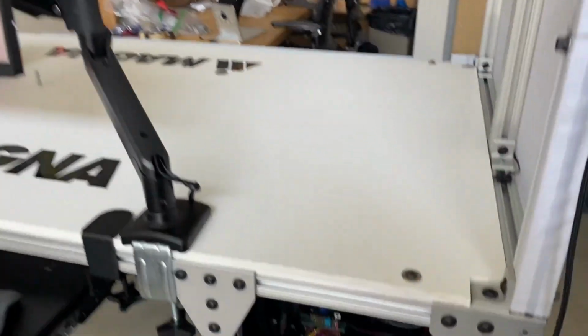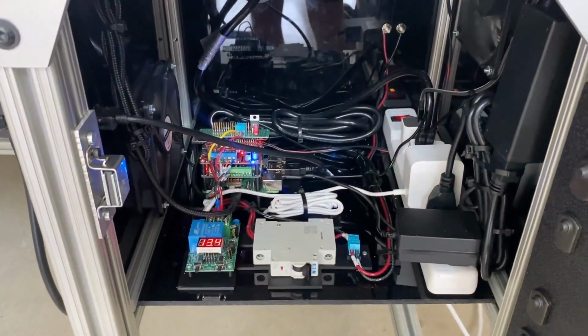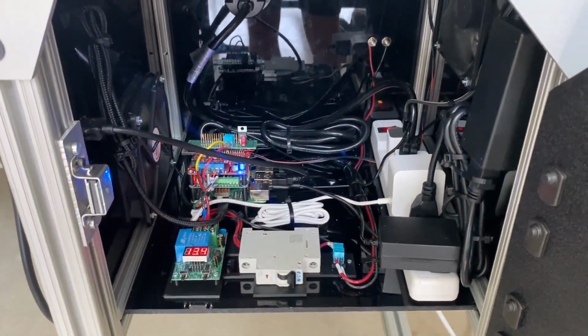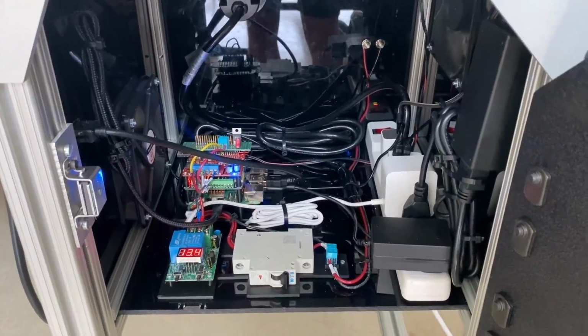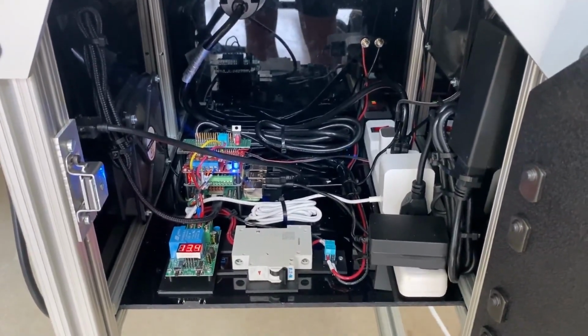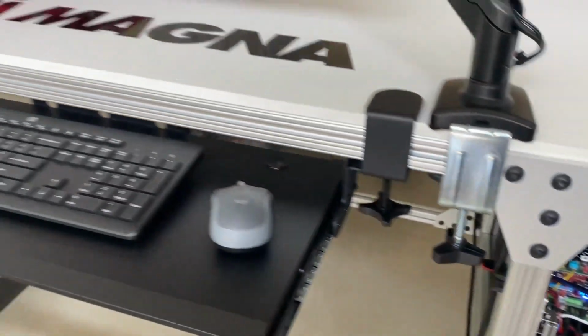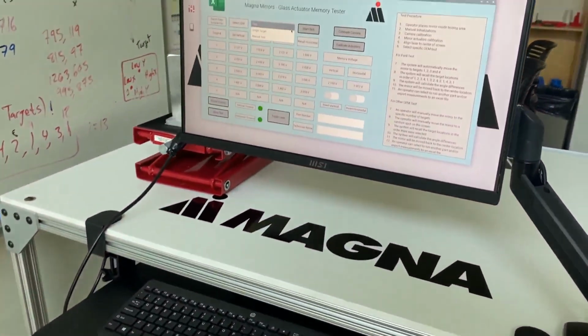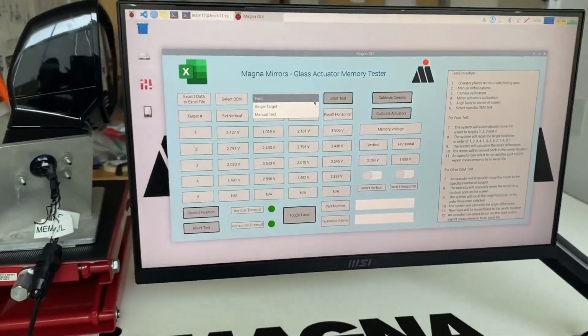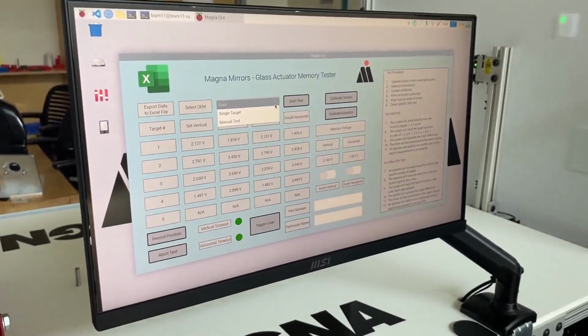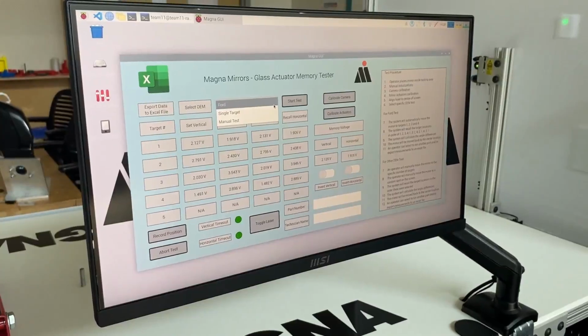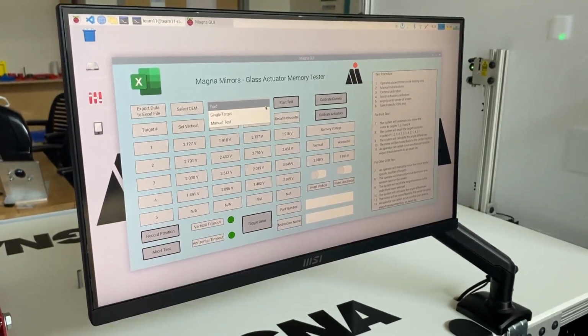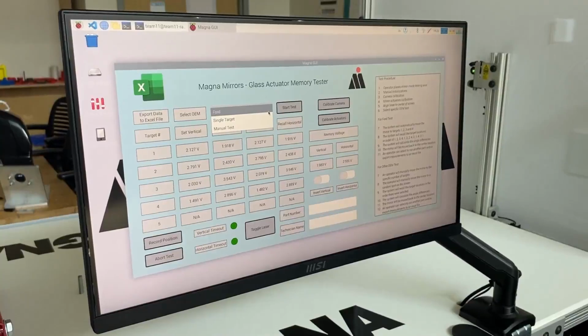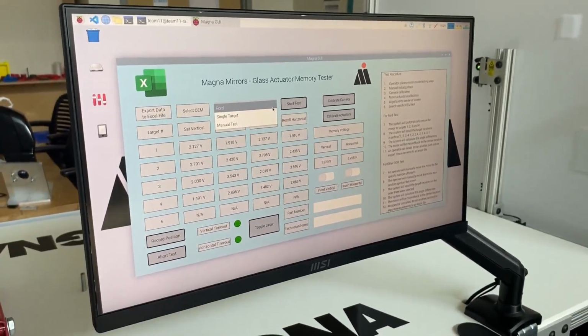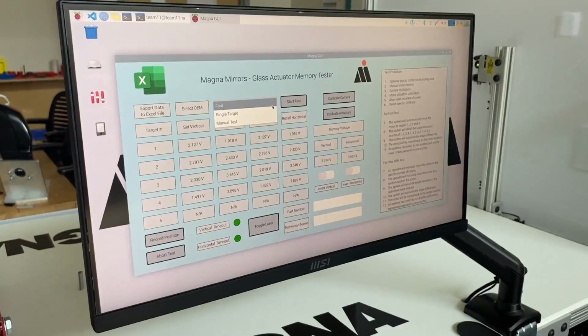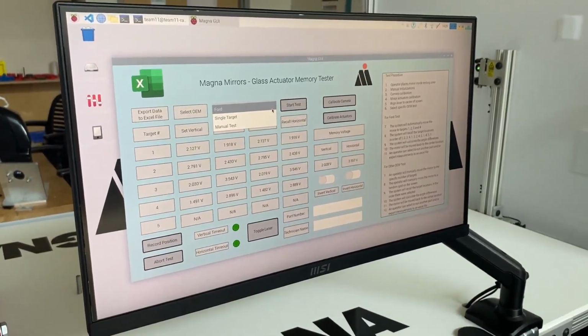Here, we're showing the electrical enclosure where we have all the electrical components involved in the system, as well as 2 fans to control the temperature inside of the enclosure. As we go back to the GUI, we can observe that the vertical and horizontal voltage values are being stored and displayed for a quick data interpretation. After each test is finished, the system stores the recorded data in a formatted spreadsheet. Once the user is done testing all the mirrors, the user can export the spreadsheet to a flash drive.